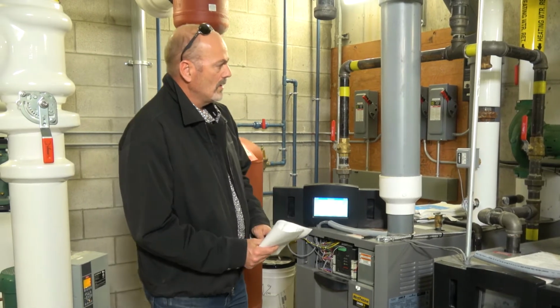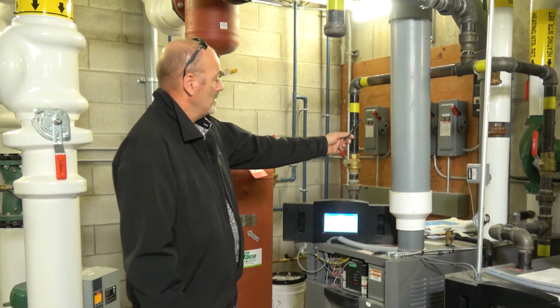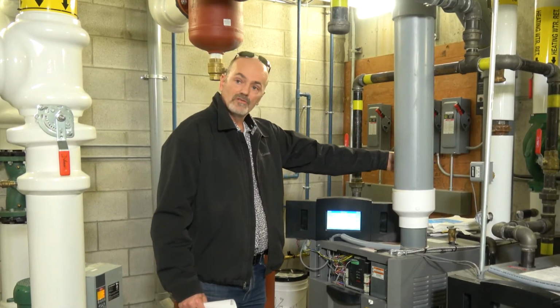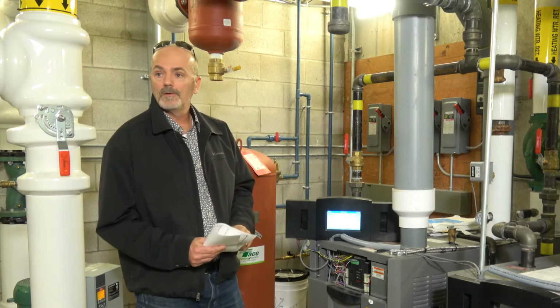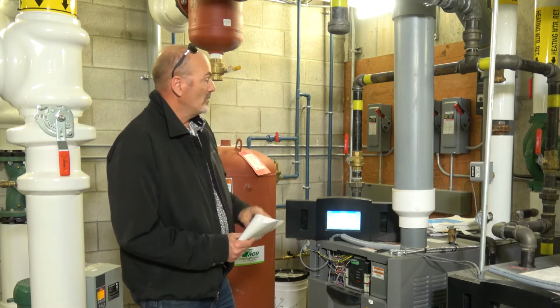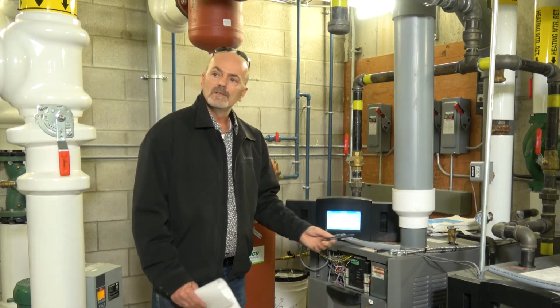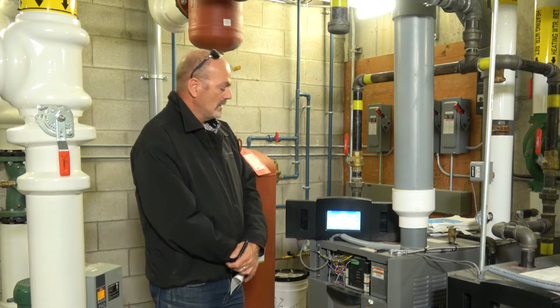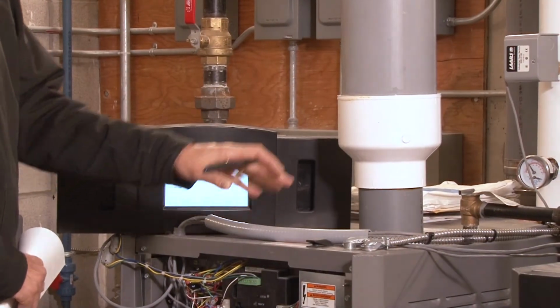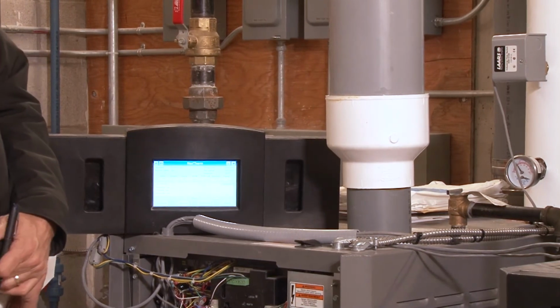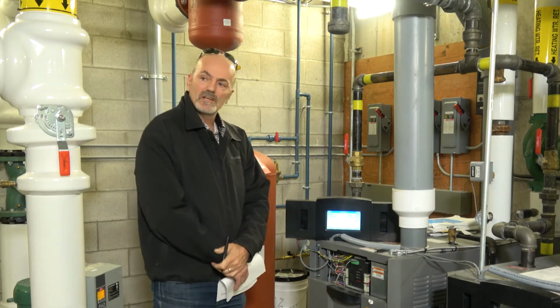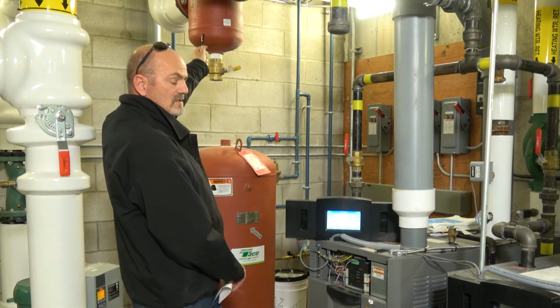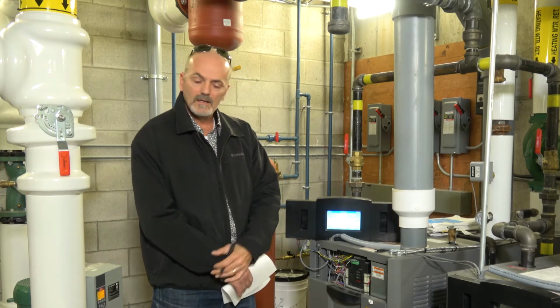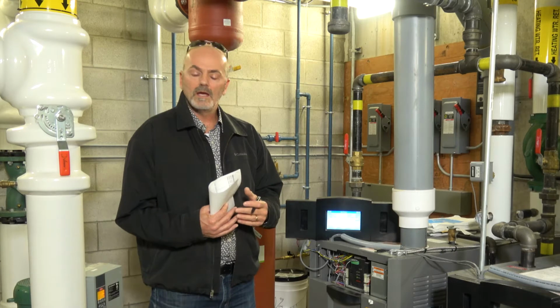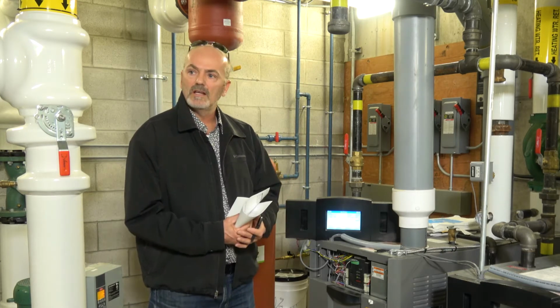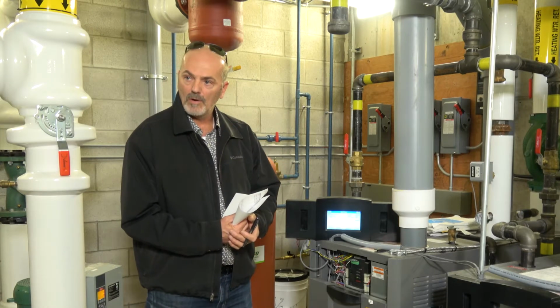So externally to the boiler, a problem could be a pump issue, a low water cutoff issue or a flow switch issue, or the pump starter failing to call the pump on. The pump starter is interlocked with the boiler, so on a call for heat based on sensors, which are installed both in each of the boilers and externally in the piping, there's a supply sensor on the secondary side of this device, and then there's an outdoor sensor outside. Between the two sensors, they monitor the temperature we have outside. This is the calculated temperature we want going out to the building for the fan coils to heat the building.